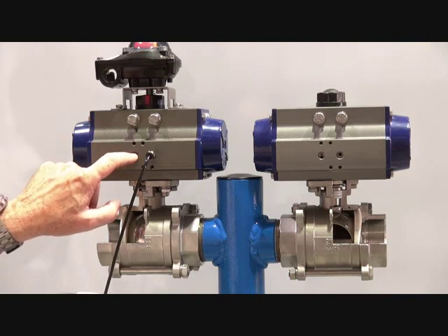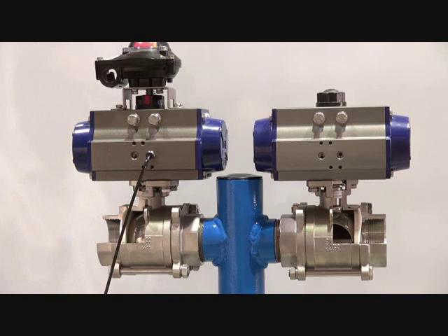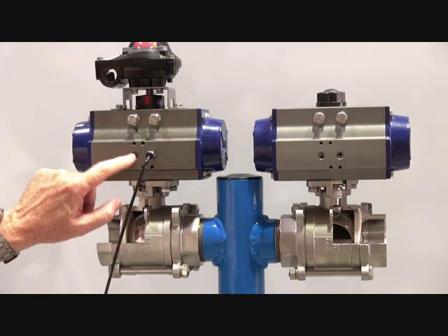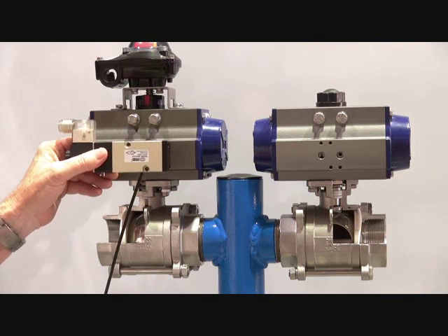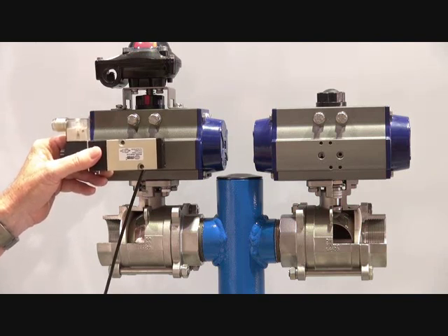We recommend a port silencer to go in here, and that allows the unit to at least stop dust being pulled into it as it's sucked back in. But it's better to operate it with a double solenoid or 5-2 solenoid like this.